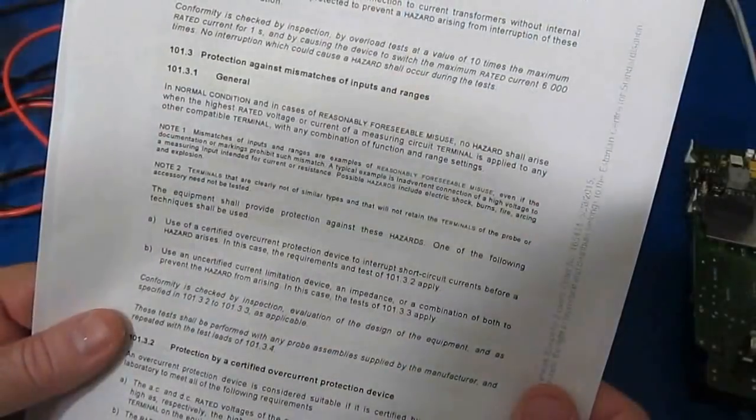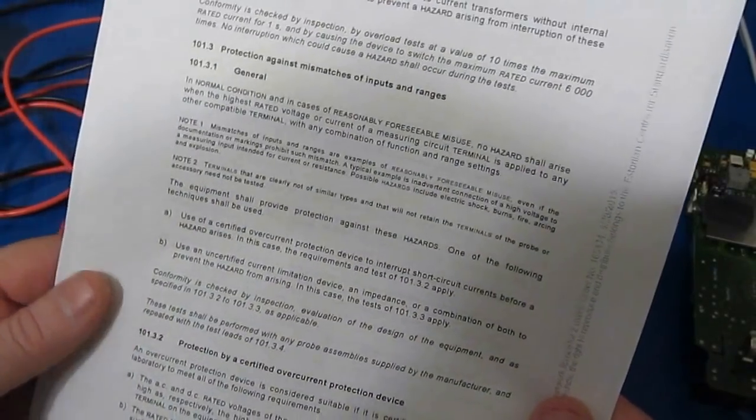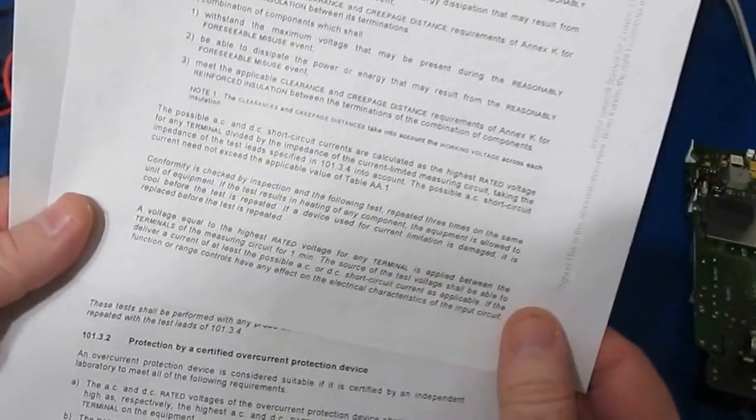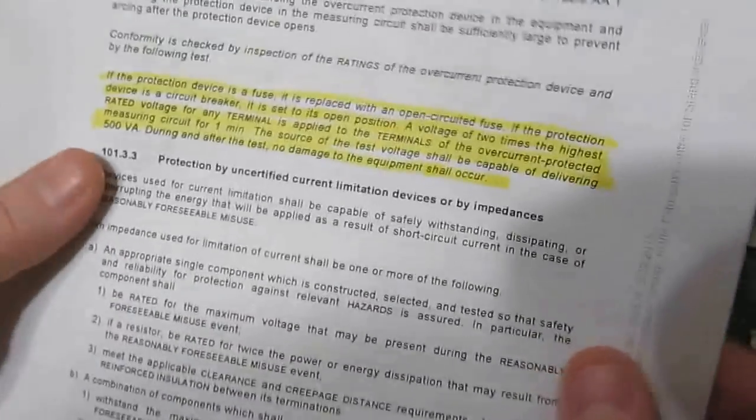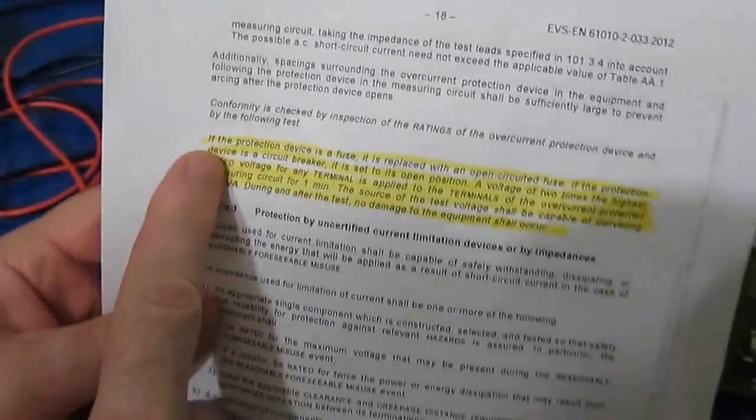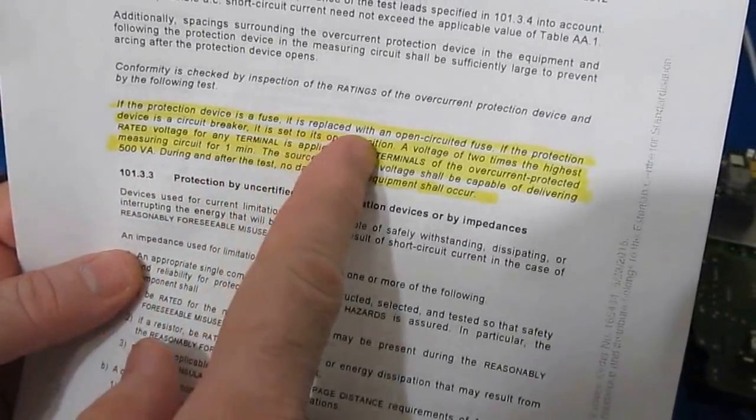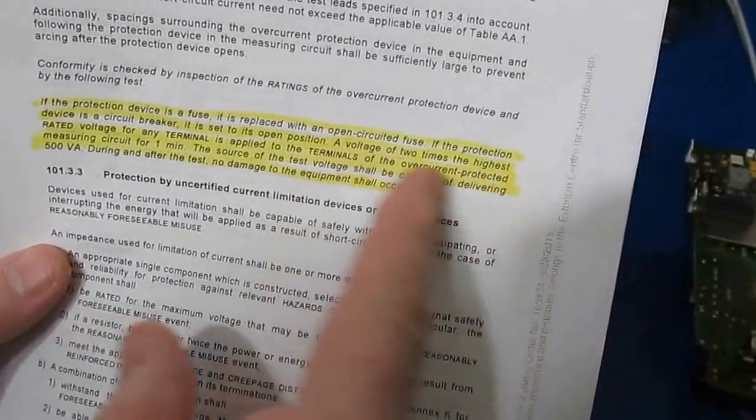This is out of IEC 61010-2-033, and this is section 101.3.2. Here we can see if the protection device is a fuse, it's replaced with an open circuited fuse.